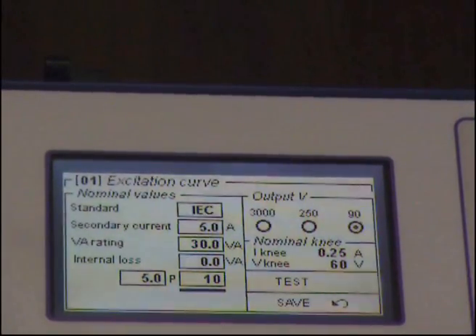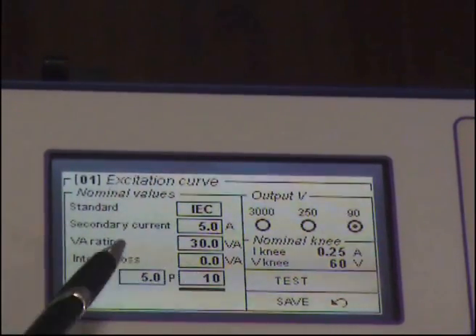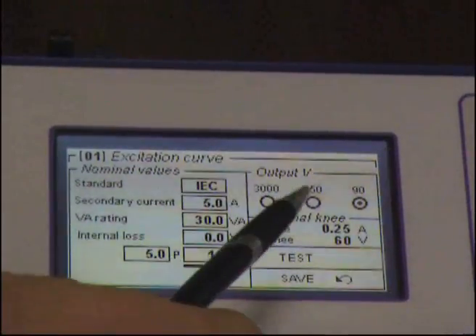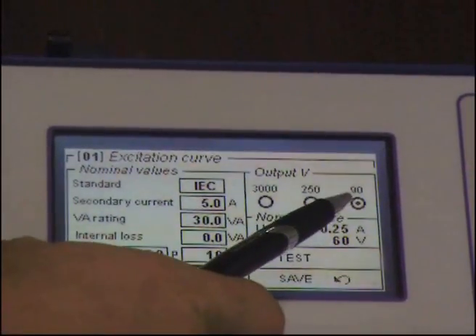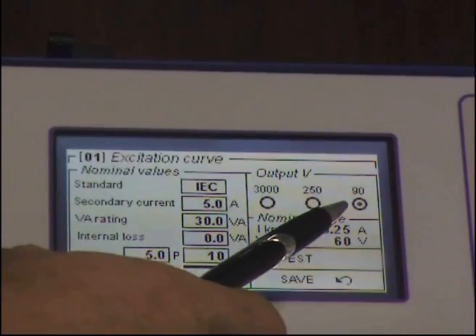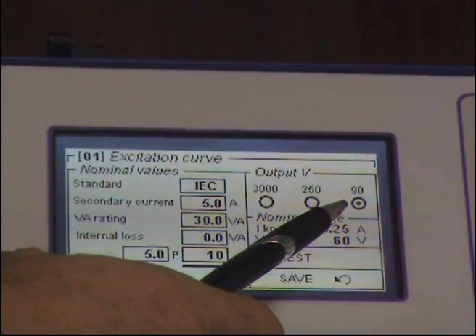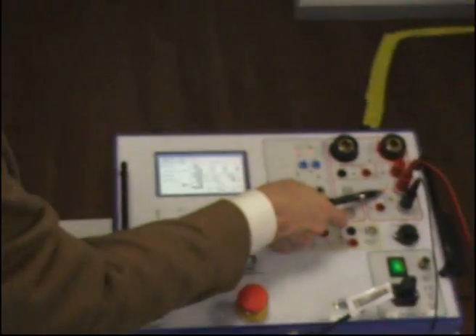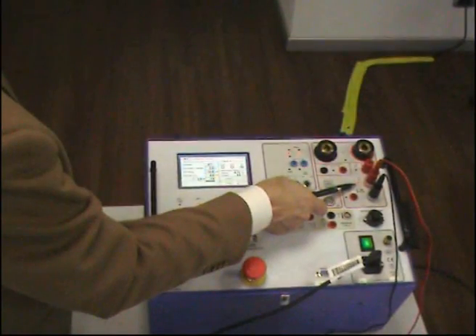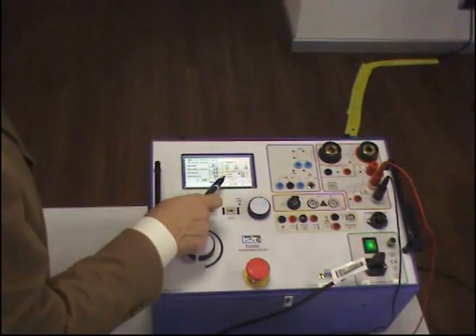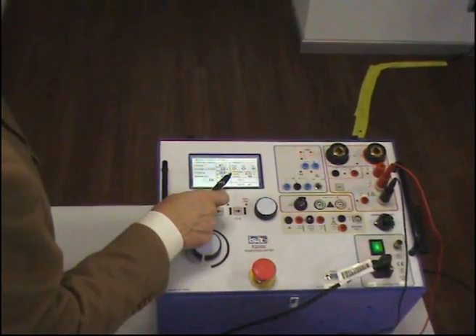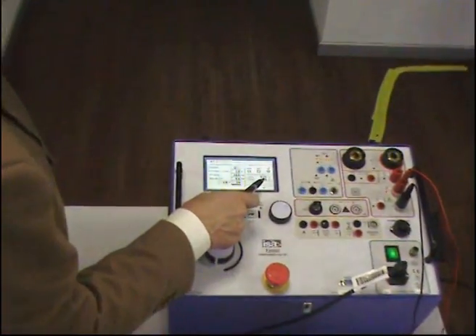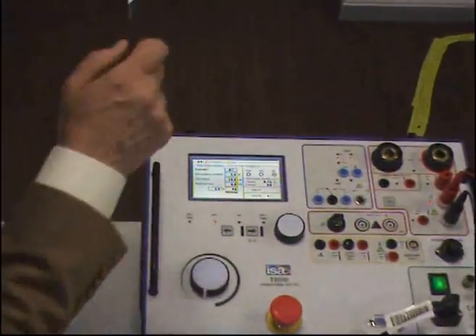Now, as soon as I have entered these values, the test set itself is suggesting to connect to the 90-volt output, and this is where I have connected it — 90 volts. It is also telling me that the nominal knee point is 0.25 amps and 60 volts.